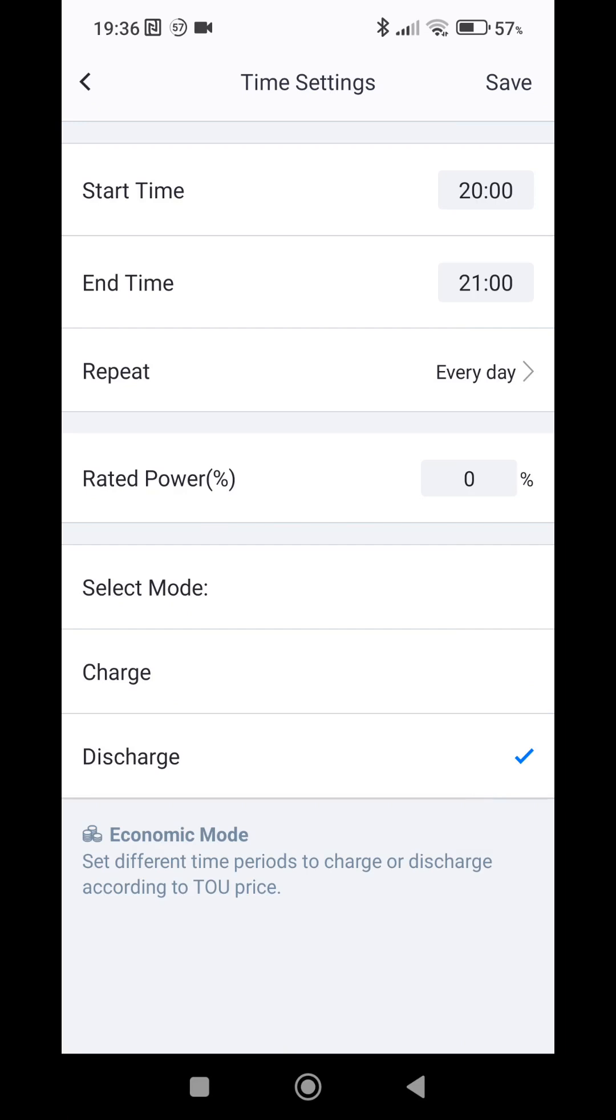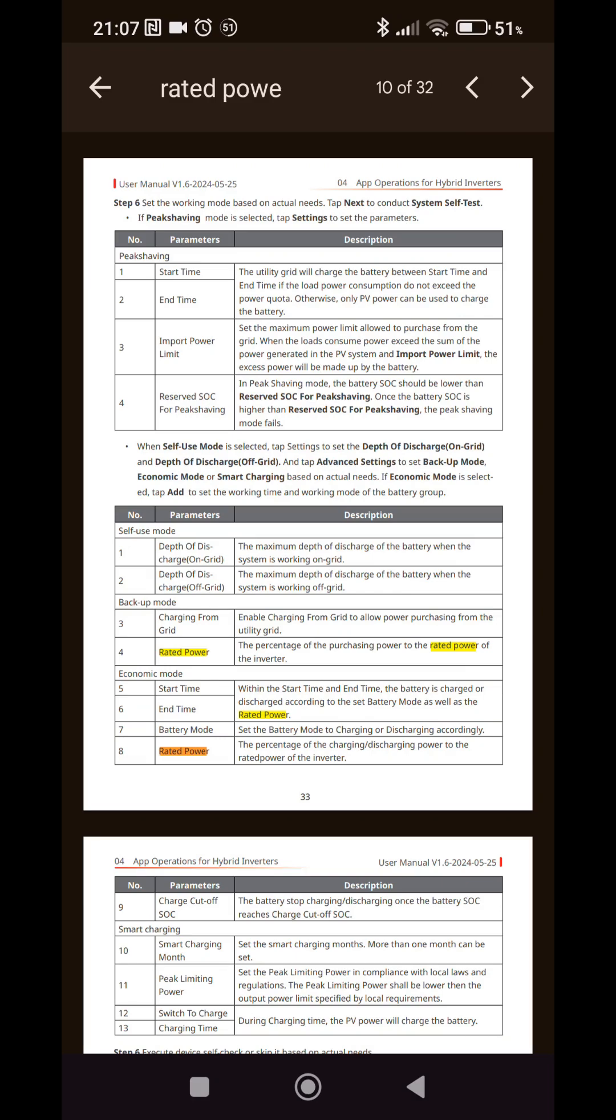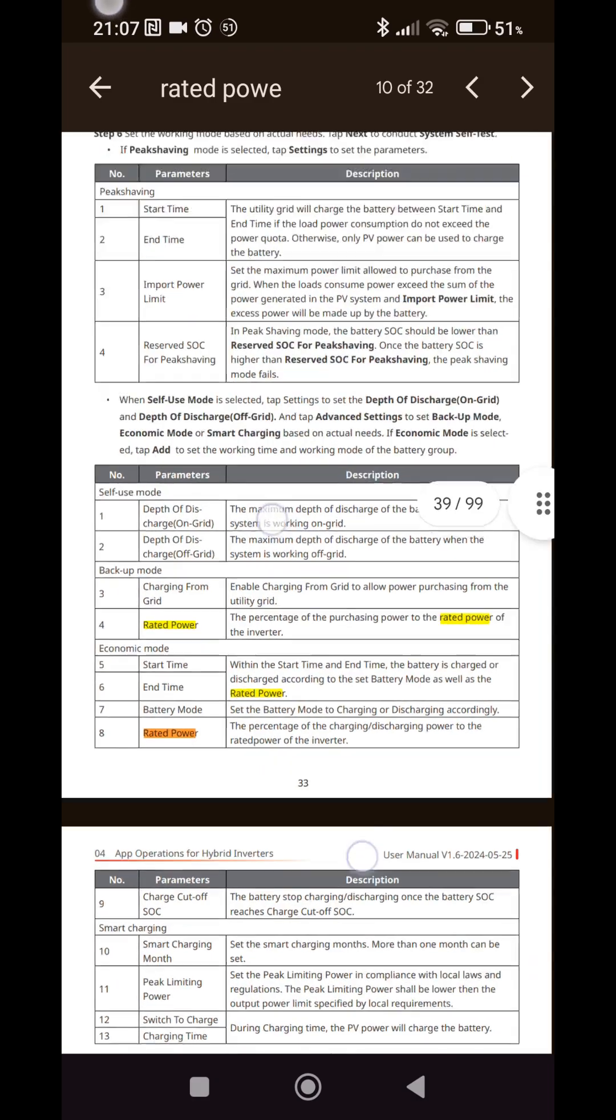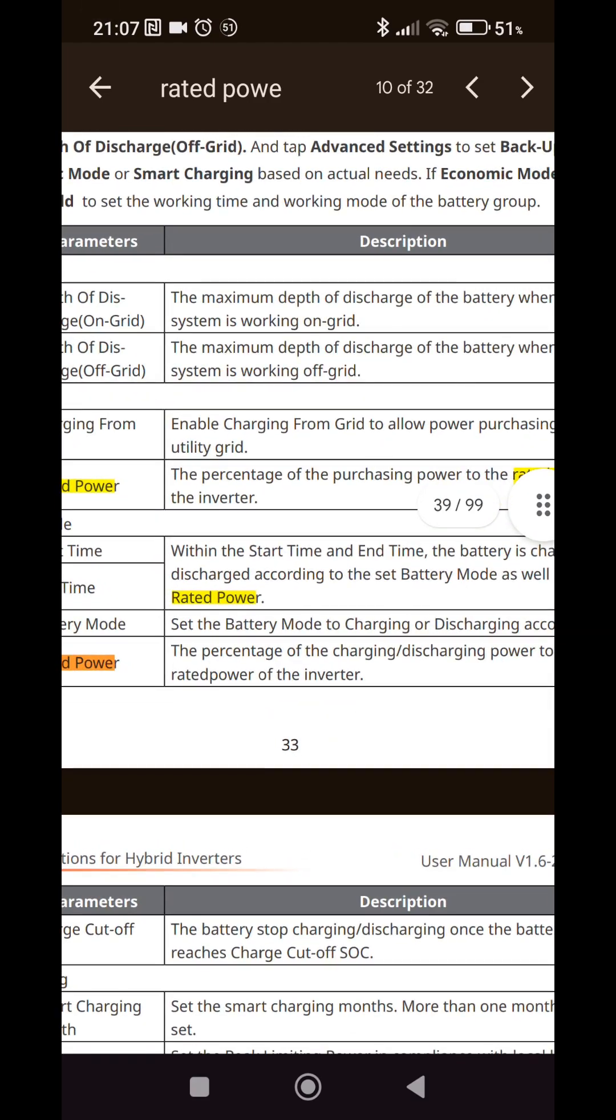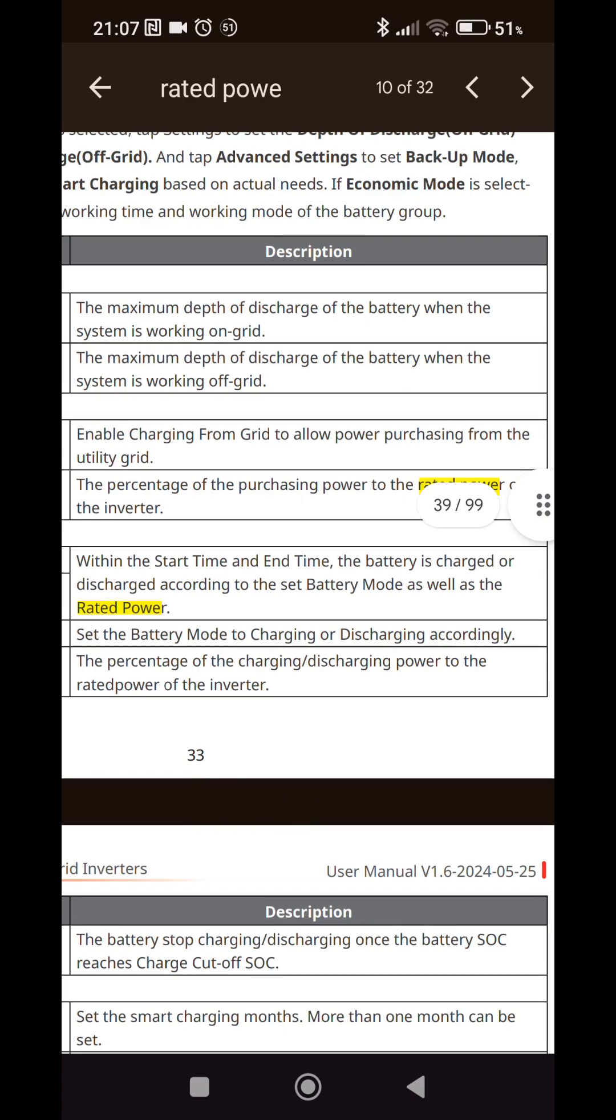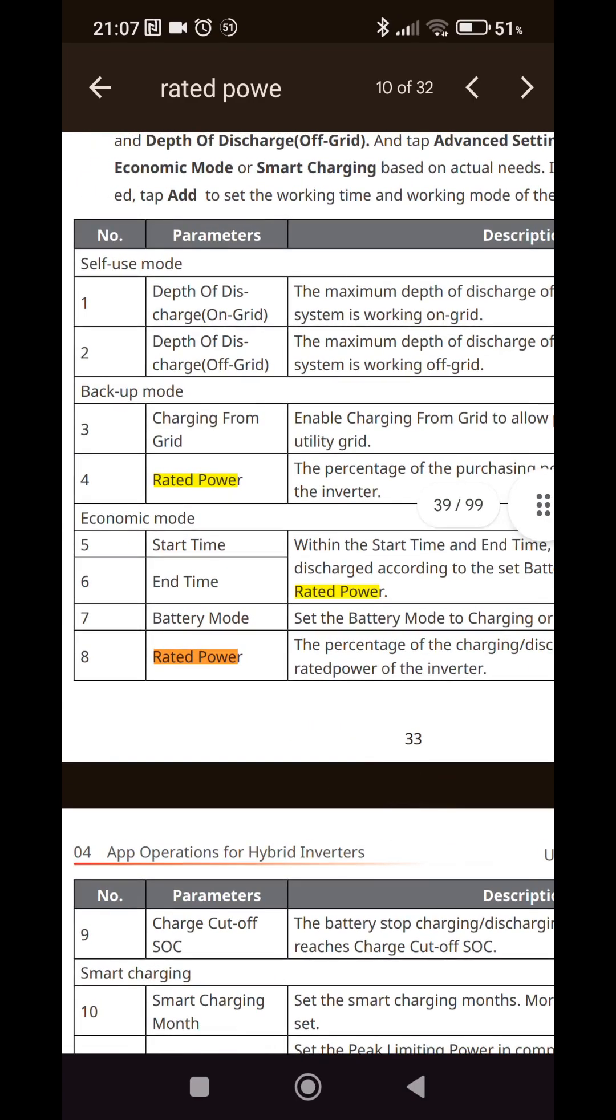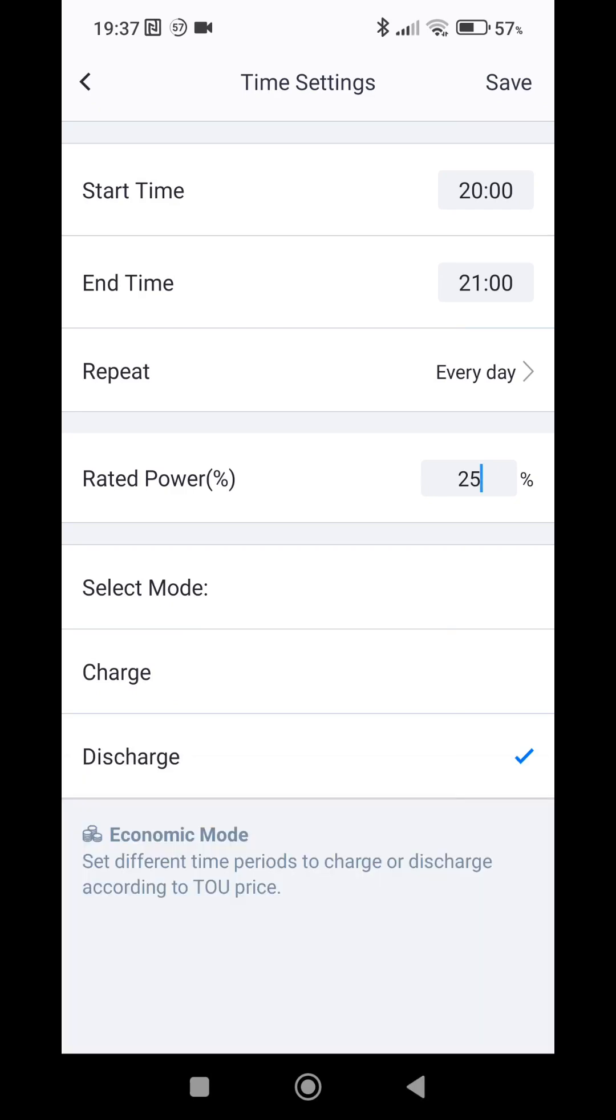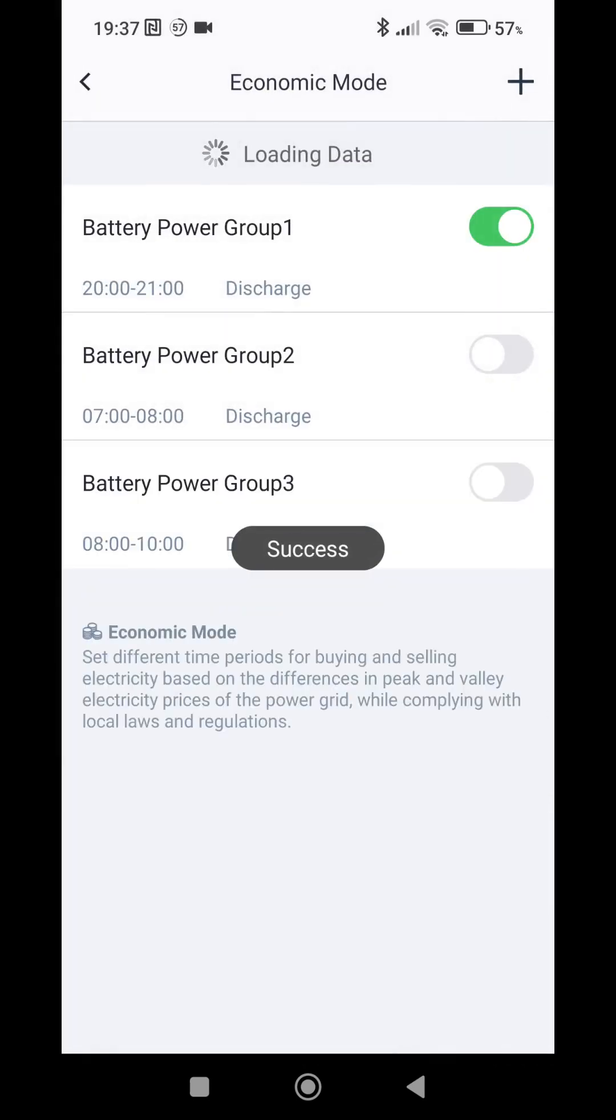We choose discharge because we want to discharge the battery. And we set the rated power in percent. As the manual says, in economic mode the rated power is the percentage of the rated power of the inverter. So in my case the rated power is 8 kilowatts, so 25% will be exactly 2 kilowatts.